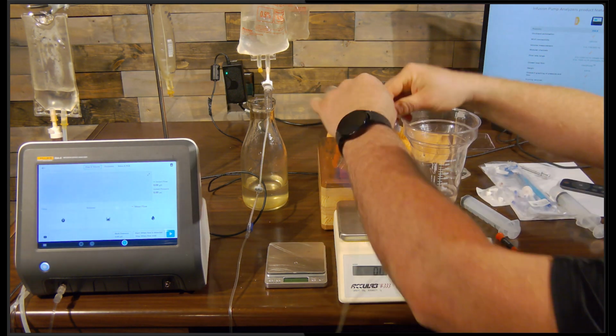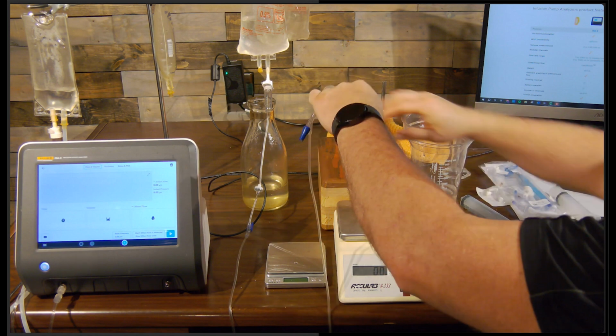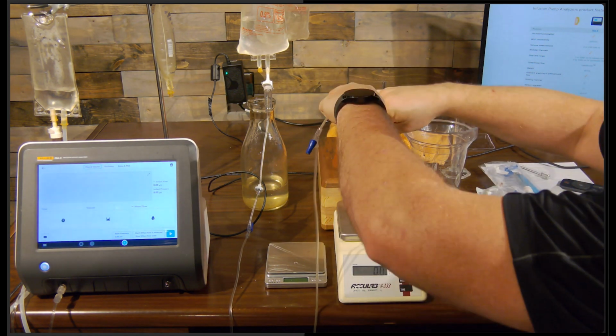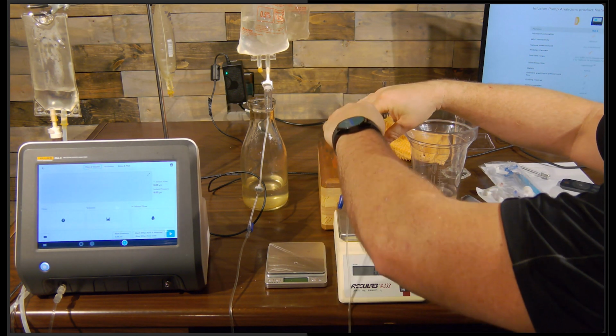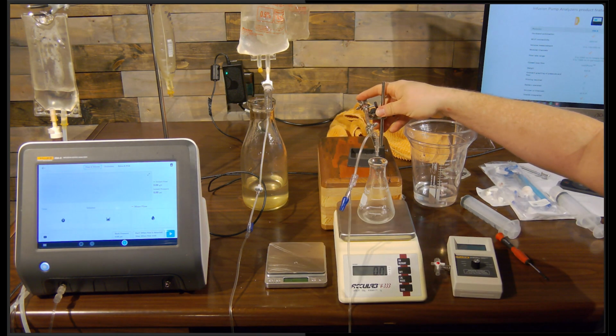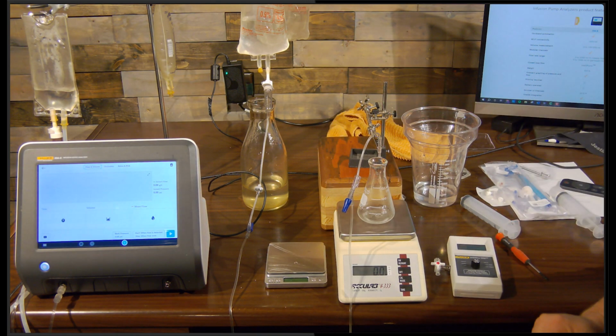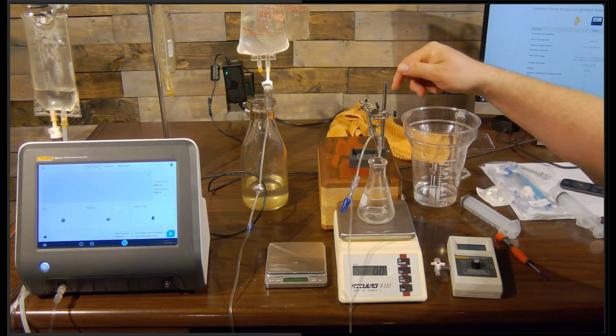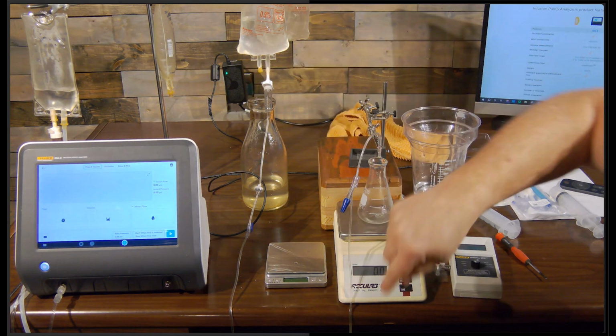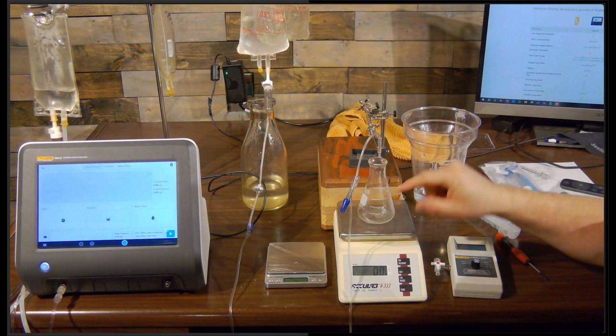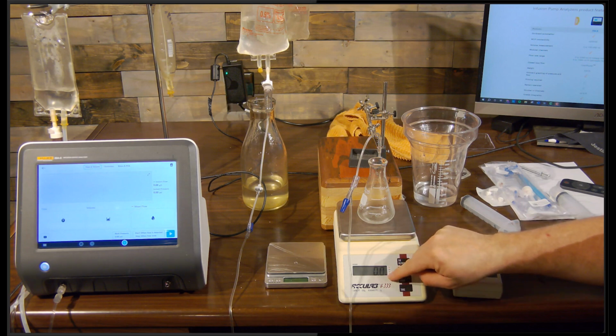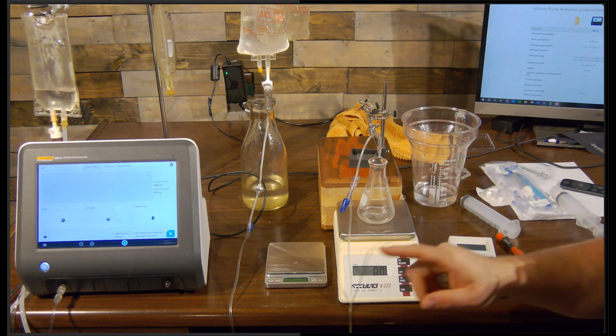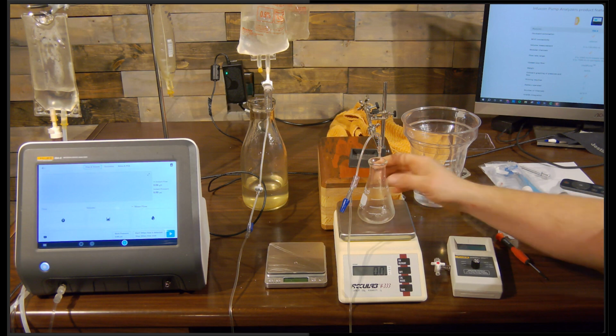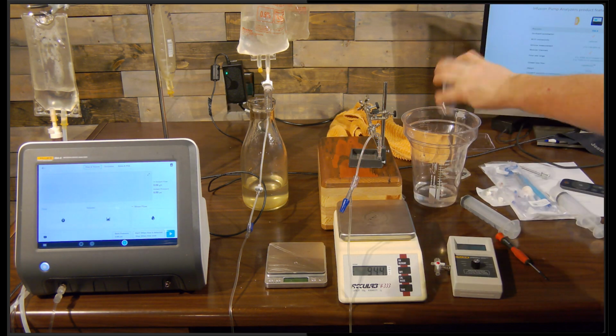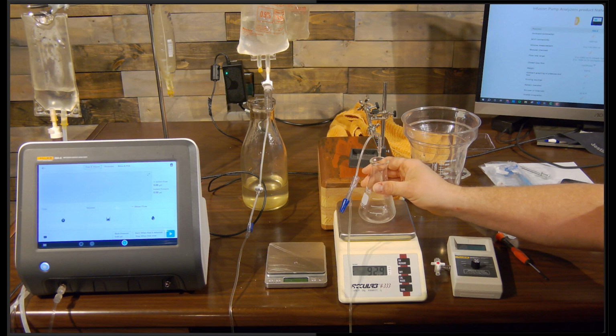And here's something I see some techs do to not have to deal with this hose in and out all the time. They'll just take a block, and this is a device for soldering wires to hold them together for you. So you could put something like that and hold it above it, and now you run your infusion pump and push the fluid in, and when you're done, it'll collect in this canister and you get your weight, as long as you have fine enough resolution. And then when you're done, you would measure that and then dump it back out into a collection canister and put it back on here.